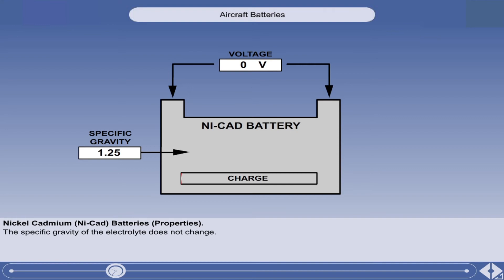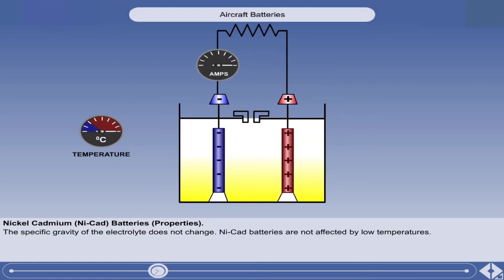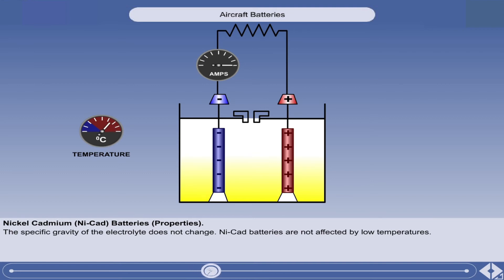The only way to determine the state of charge is to carry out a measured discharge test or capacity test. Nickel cadmium batteries are not affected by low environmental temperatures in the way that lead acid batteries are, and because the specific gravity of the electrolyte remains high, there is no danger of it freezing.